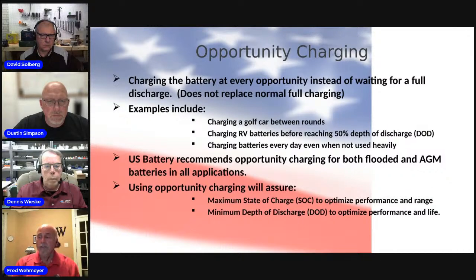However, if you have an application, and this is something we highly recommend, where you can manage depth of discharge, for example, if you cut that 80% in half to 40%, you would expect to get about twice the cycle life. Actually, you get a little interest on your investment there. You get an extra 15% if you do that. So that 600 to 700 cycles is more than doubled to over 1,500 cycles if you can keep your depth of discharge below 50%. Okay. Next slide.